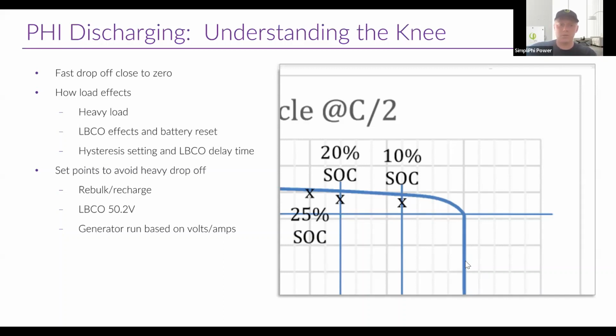You don't want to set your low battery cutout too low. The BMS does have protection for this, but again, if you've got a large load, then you can draw the batteries down so quickly that sometimes the BMS isn't even able to catch it, especially if this is a repeated thing where you're doing it over and over to the batteries.